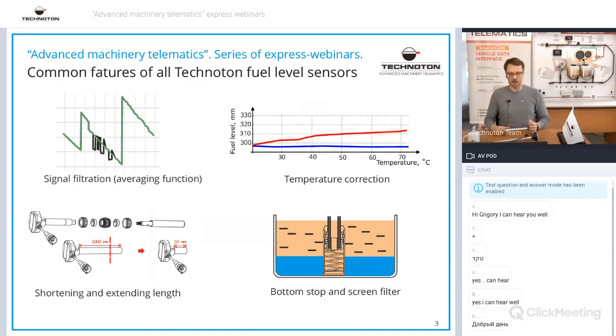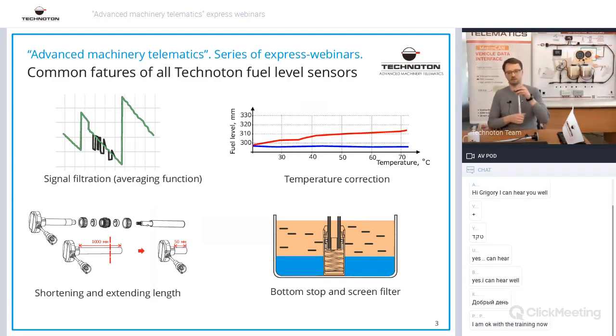And of course there's the bottom stop and screen filter. The bottom stop prevents the fuel level sensor from moving left and right due to fuel tank vibrations - it's a spring fixed at the bottom of the probe that makes the installation more rigid.